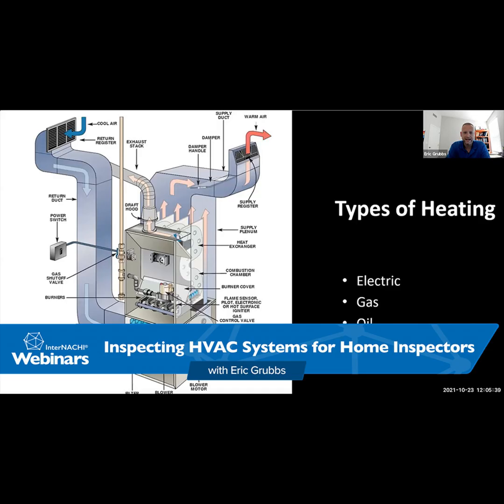So it doesn't really damage it. It's just going to be slightly acidic compared to normal condensation from an air conditioning coil. And some codes, depending on where you live in the country, may have some regulations on it. I can tell you from the manufacturer's standpoint, they're going to tell all their technicians to just run it, but also be cognizant of the septic system codes of wherever they're installing that piece of equipment. But as far as hurting it, no, it's not going to do any kind of damage to it.